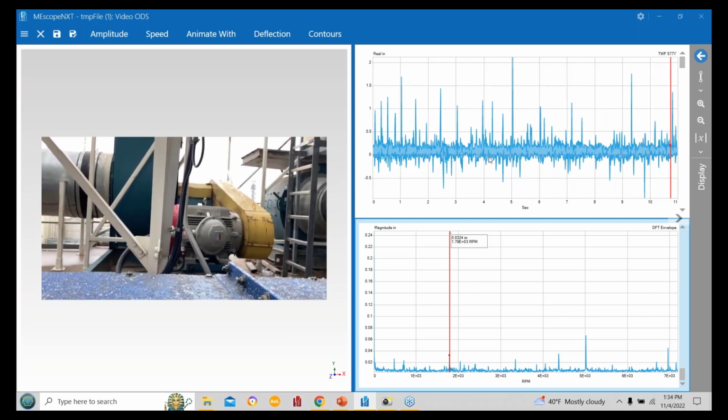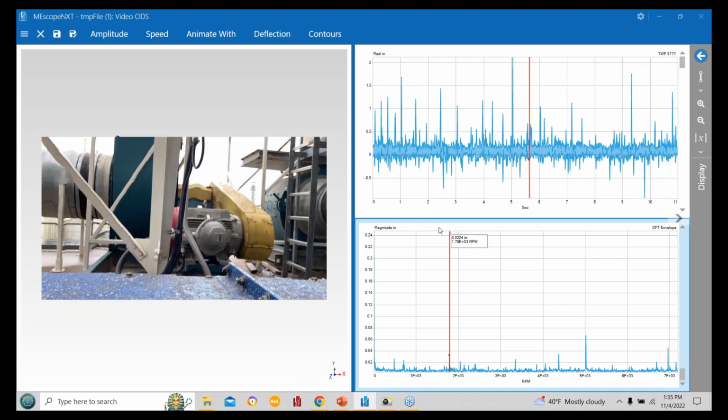There are some applications for the time waveform for orbits and things like that. It really works well. It's just getting access. So in this case, guards had to be on. We couldn't even see the bearings. They were behind the guards. So a little difficult sometimes. But the background removal works really well here.